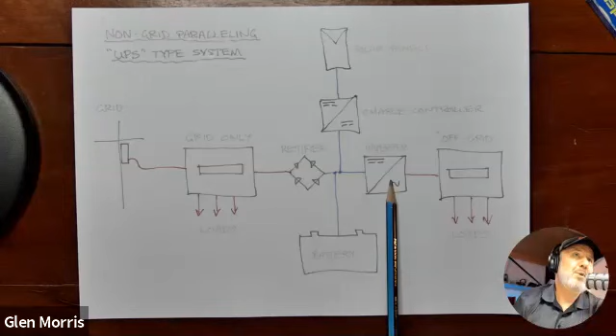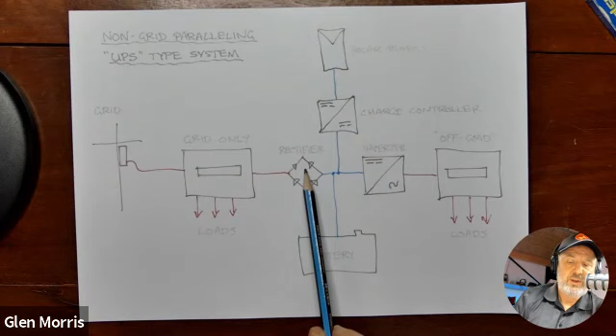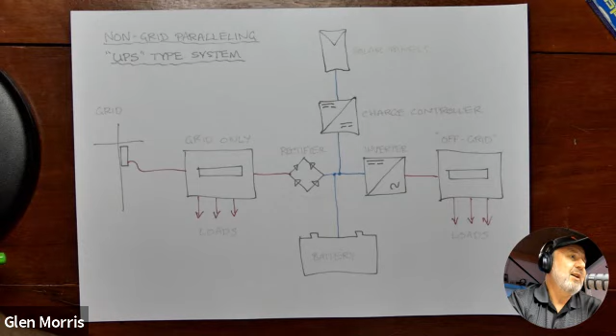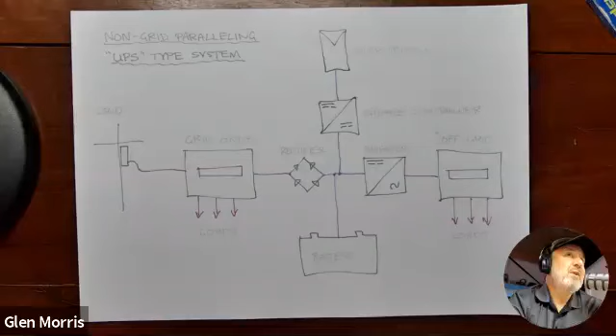is where they've got an inverter that doesn't parallel with the grid. They have batteries and they have solar, but what they've got between the grid and their batteries is just a rectifier, a battery charger. So as far as the utility is concerned, the customer has installed a battery charger. There is no reverse flow of power. There's no paralleling with the inverter, with the grid, so it can't affect its safety or operation. And therefore, in Australia, there's no utility limits on this.